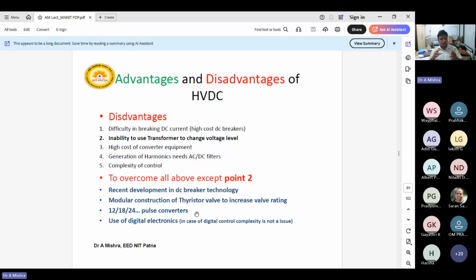Further, the 12 pulse converter is using 12 devices, but that is not the exact reason. In a 12 pulse converter, in a complete cycle of output voltage, we will see 12 pulses, and each pulse duration will be 30 degrees for a complete cycle of 360 degrees. So if you are increasing the pulse number of the converter, you will find that your power quality is increased. Harmonics will be reduced, and the voltage level will be good.